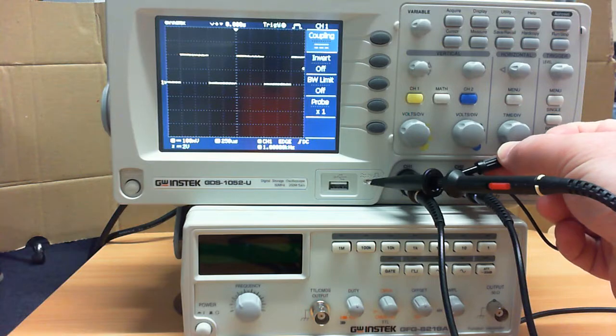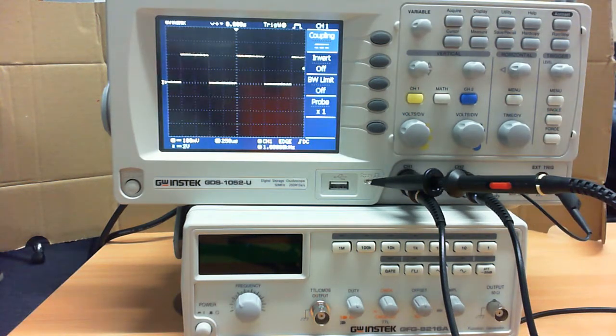What are you getting there when it's just right? What you're doing there is, the coax cable that's in there has the signal in the center, and the outer shielding, which is our earth in this case. At high frequency, we get a capacitance effect between the two of those. That pot is not a resistor. It's a variable capacitor. So we're adjusting an offset capacitor. The capacitance we get between the signal and the shield is called a parasitic capacitance. It's one we don't like in the system, but it's there because of the nature of the cabling. So if we can trim an offset capacitor that balances it out, we're negating that parasitic capacitance, and we're just getting our nice signal.